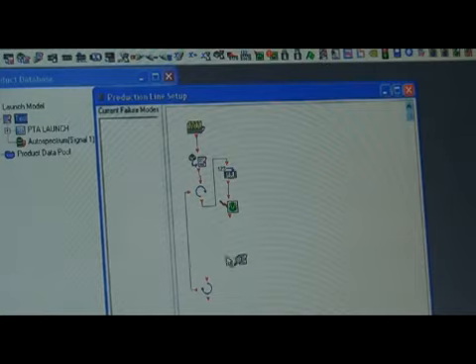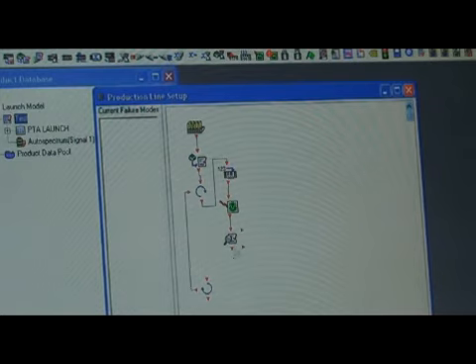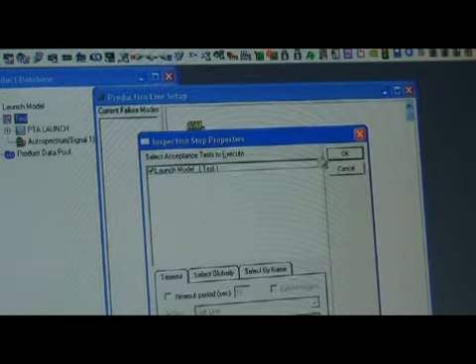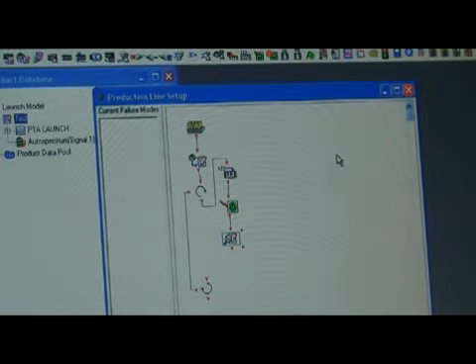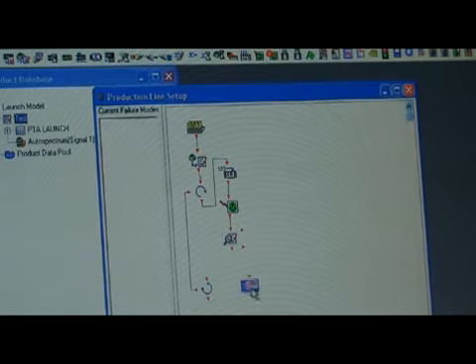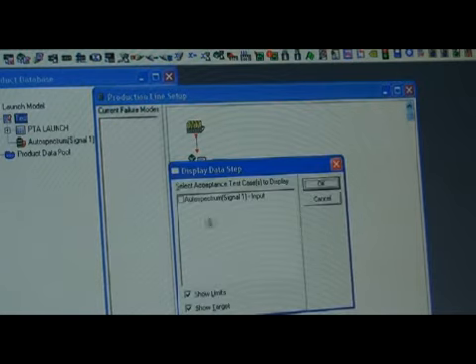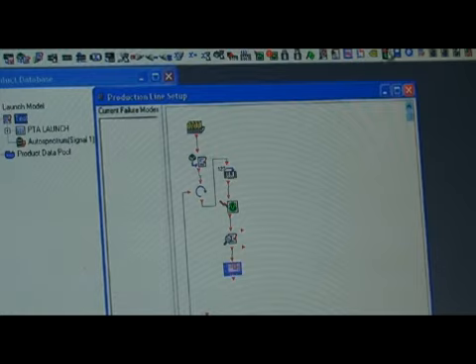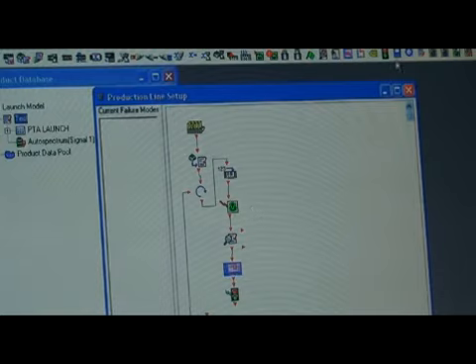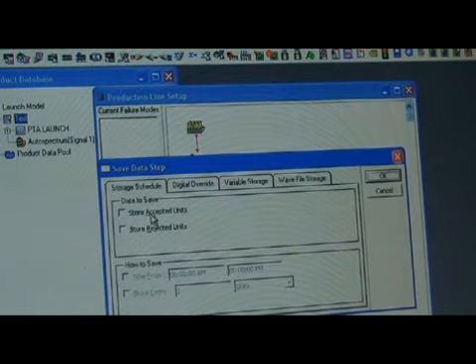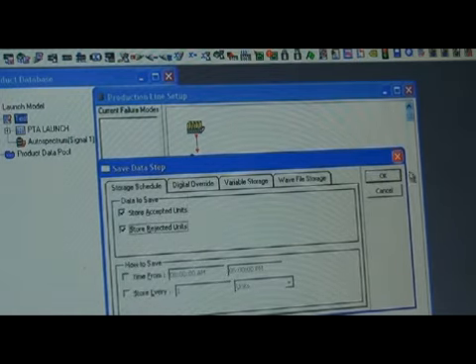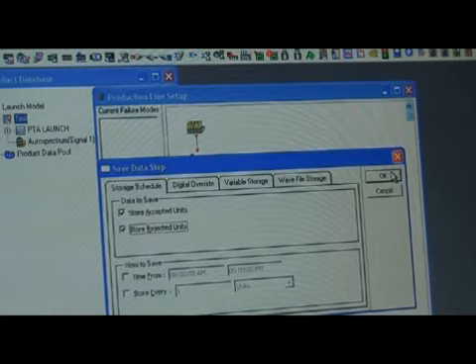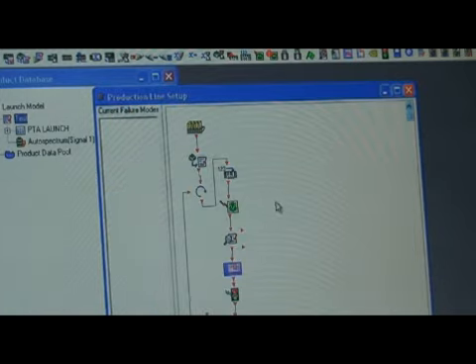Put an inspect data. In this case, our third octave spectrum is a linear average. As soon as the linear average is complete, inspect the launch model data. We'll bring up a display. We'll tell it we want to display autospectrum one. We'll actually compute the, we'll tag the data with some go, no, go information. We're going to save the data to disk. Set the properties of that to store accepted, store rejected. There's all kinds of parameters we can set. Those parameters will be defined whenever you learn more about those as you go through training.